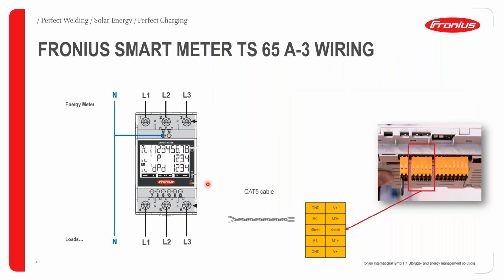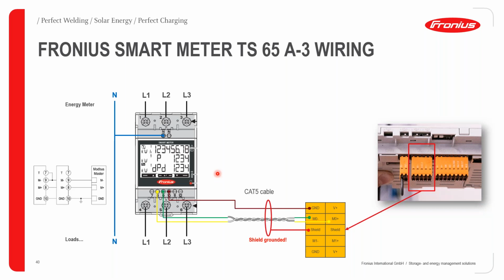Good. I mentioned that it's supposed to be connected to the smart meter because that is your means of getting a wholesome view of your connection. So please ensure that your smart meter is appropriately and correctly connected. For the smart meter connections, it's on terminals 8, 9, and 10, which represent M0 plus, M0 negative, and of course ground respectively. Please ensure that your shield is connected appropriately. And then to complete the communication gateway for the smart meter, all you need to do is loop terminal 7 to 9. By doing this, you automatically activate the 120 ohms termination.